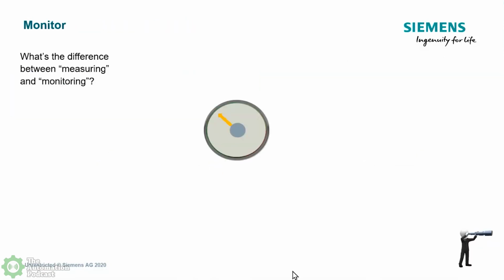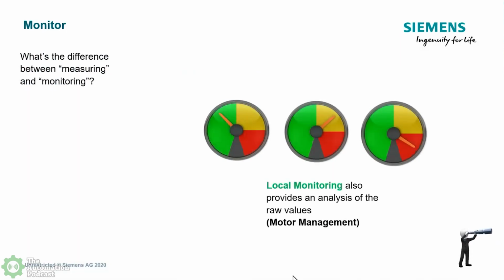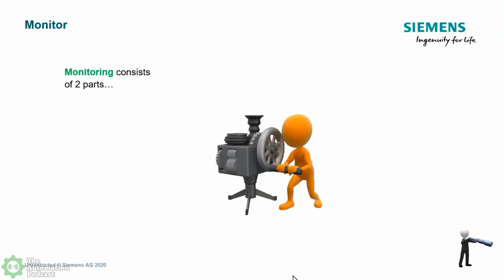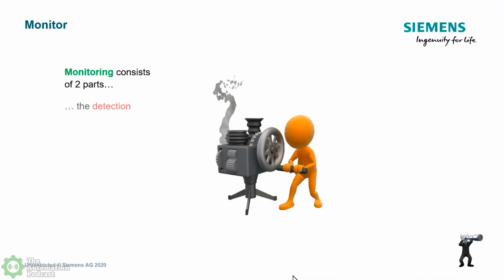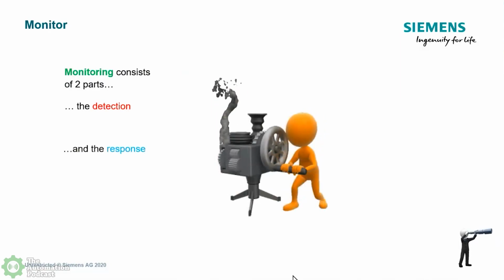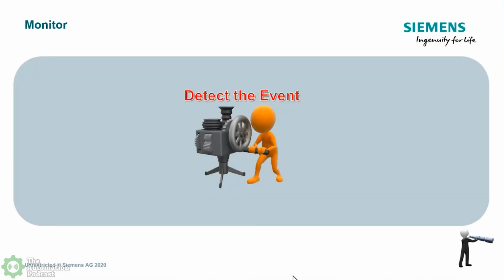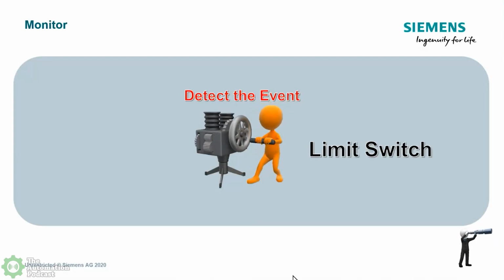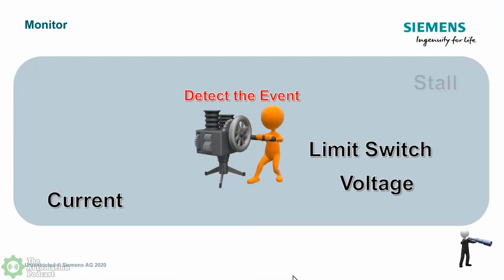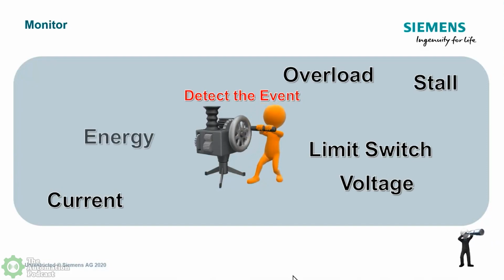So to move on to the next slide, what can the SIMOCODE monitor? What can it give you? What information can it give you? Well, there are multiple things that we can do. We can do local measurement, or it can become a remote IO for you. And with that, we can bring in raw values and analyze and give a complement to the motor management system. And we're going to show you some of that. But the key to it is also the flexibility: when we're monitoring and detecting, what do we do with it? What will be our response? So the flexibility with SIMOCODE is to be able to detect and then customize our response to maybe some type of problem or just some type of maintenance requirement, for preventive maintenance and so forth.